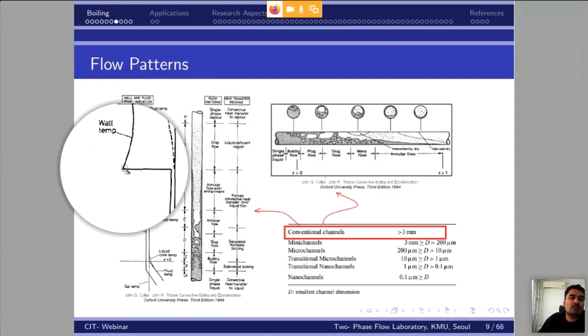At one particular point the temperature suddenly increases, peaking up. This point is called the dry out point, where the annular flow breaks and the thin film breaks. It suddenly jumps to a higher temperature point, the dry out point. After that, there is a gradual or sudden increase in wall temperature, which must be avoided at any cost since it will damage the system.